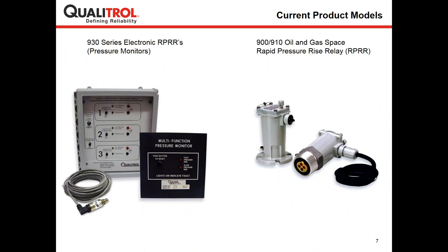So our current product lines that we offer that go on your transformer to protect and look at sudden pressure changes are, on the left-hand side, you have your 930 series electronic pressure monitor. Now you can look at 1 pressure measurement or look at a 2 out of 3 logic pressure measurement by having either 1 or 3 pressure transducers. On the right-hand side, you have the rapid pressure rise relays, which are series 900 and 910, and they can be used both on the oil or the gas space.